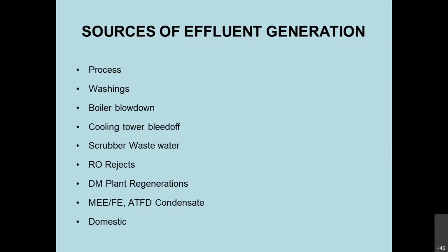Boiler blow down: every boiler is fed fresh water. Over a period of time, the fresh water is converted into steam, and whatever TDS remains settles at the bottom—that is called blow down. So every boiler requires, once in a week or once in a month, to blow down the wastewater. This may sometimes be low TDS or sometimes high TDS, based on the inlet TDS levels of the water you are feeding to the boiler.